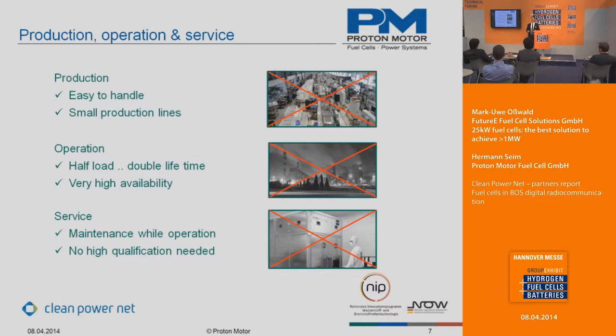And what we also generate this way is a very high availability, because every module by itself, or every system, is its own system. It can run on its own, and we have very high redundancy, so it gives us very high availability for the system. And last but not least, service maintenance is possible during operation — not of the system itself, but if you see it as a whole power plant, we can maintain one rack even if all the other racks are still running. So if we have 1 megawatt, 20 racks, one rack is off, 19 racks are still running.